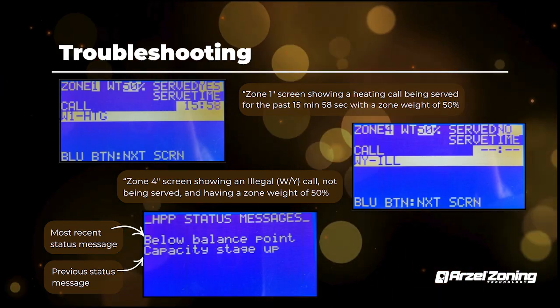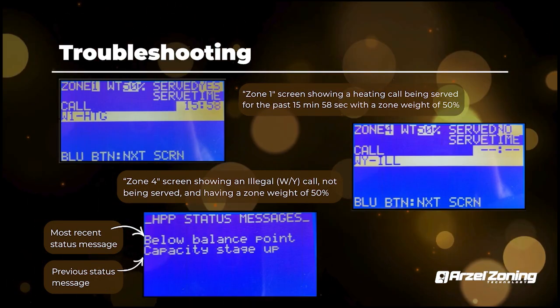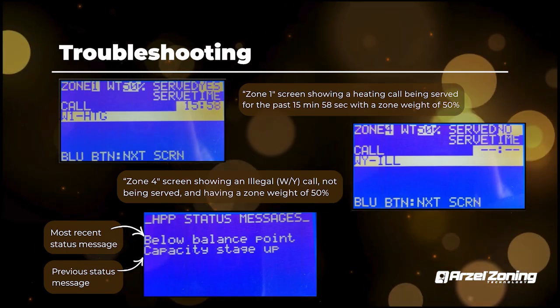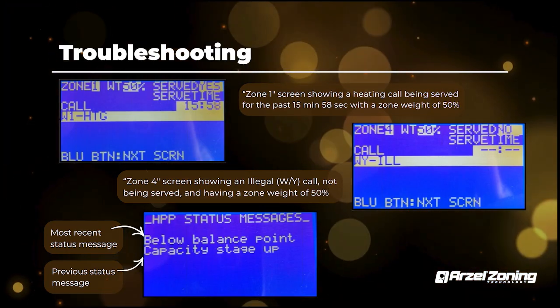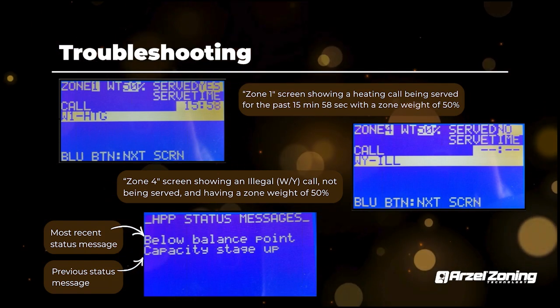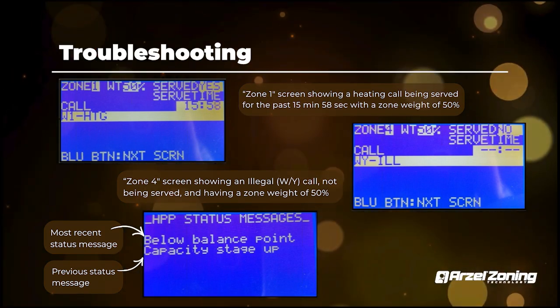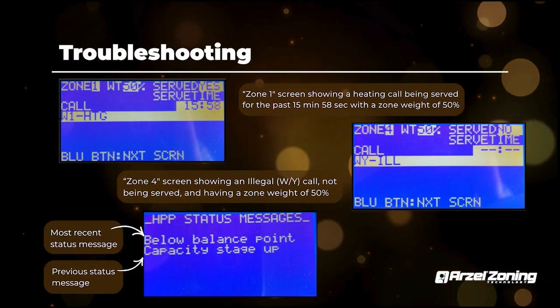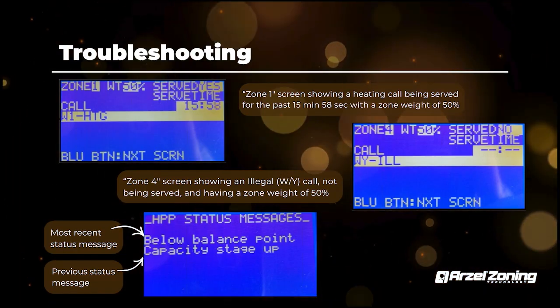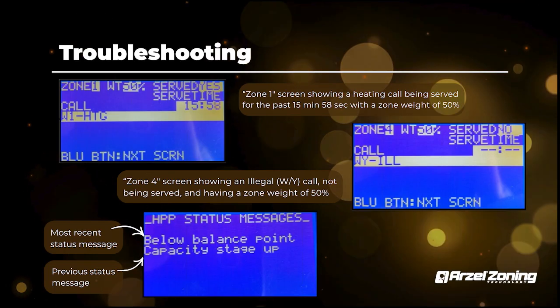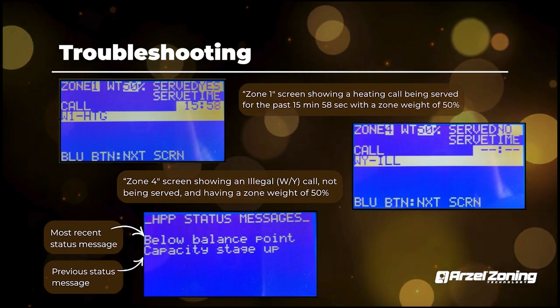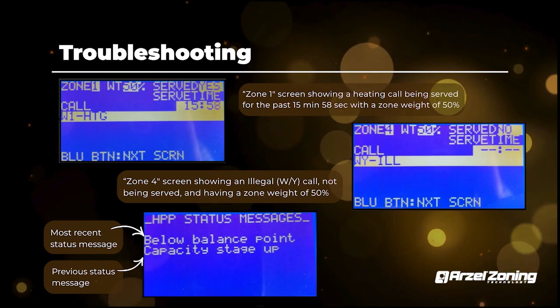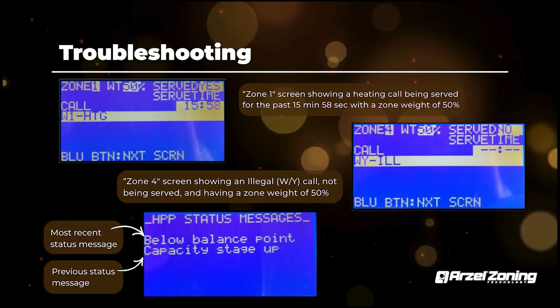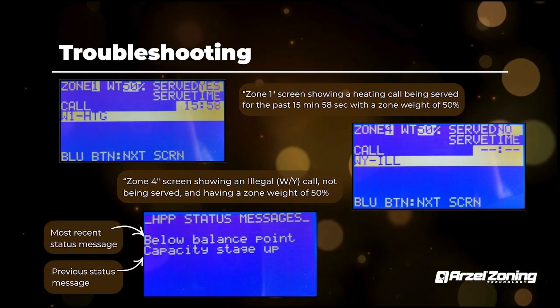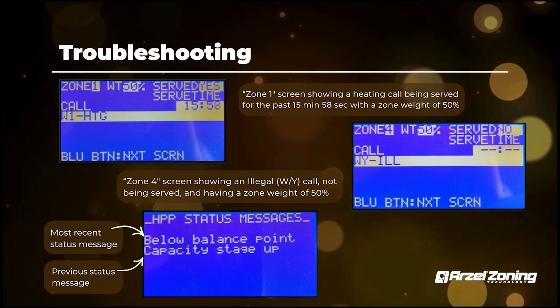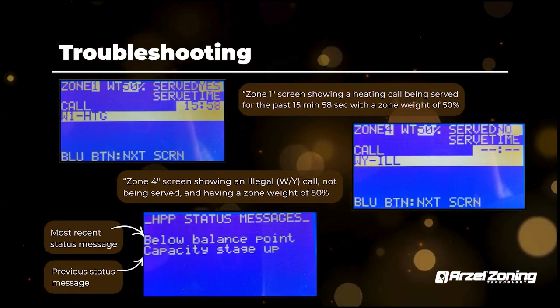The other time you'll see this is if you don't have a heat pump and you have the panel set for conventional gas furnace air conditioning, anytime you get a call for heat then, you'll see that message and it's essentially telling you we're running the gas furnace because we don't have a heat pump. Keep that in mind. That's what that actually means. And then right underneath that is capacity stage up. So in this case, we weren't able to hit our heat stage threshold, so we engaged our second stage heat. That still wasn't able to keep up, and we either switched over to our secondary heat source or it got too cold outside at that point. So keep in mind, they're not errors, they're just messages, exactly what we're actually doing in the equipment. Thank you.